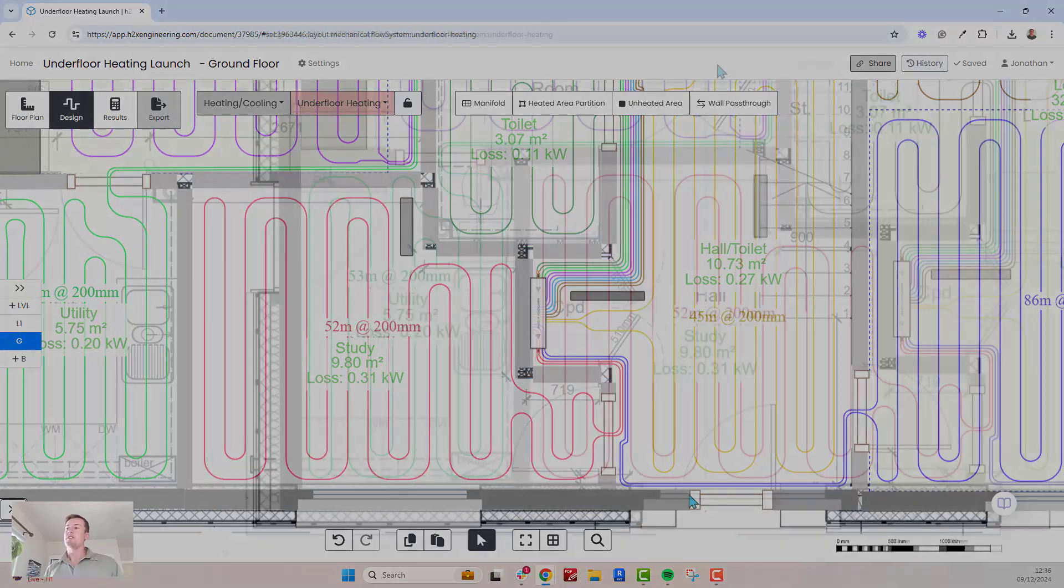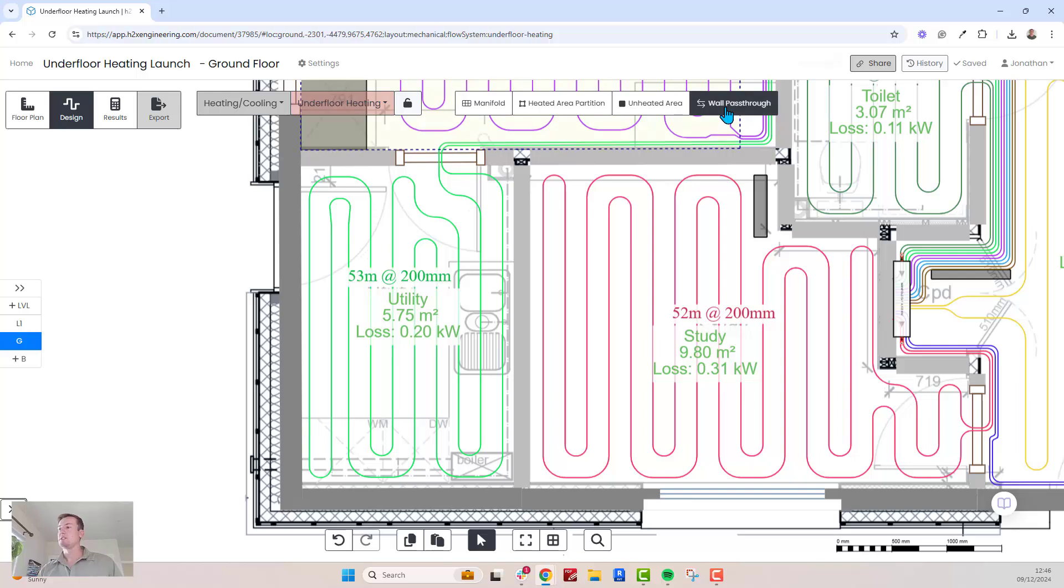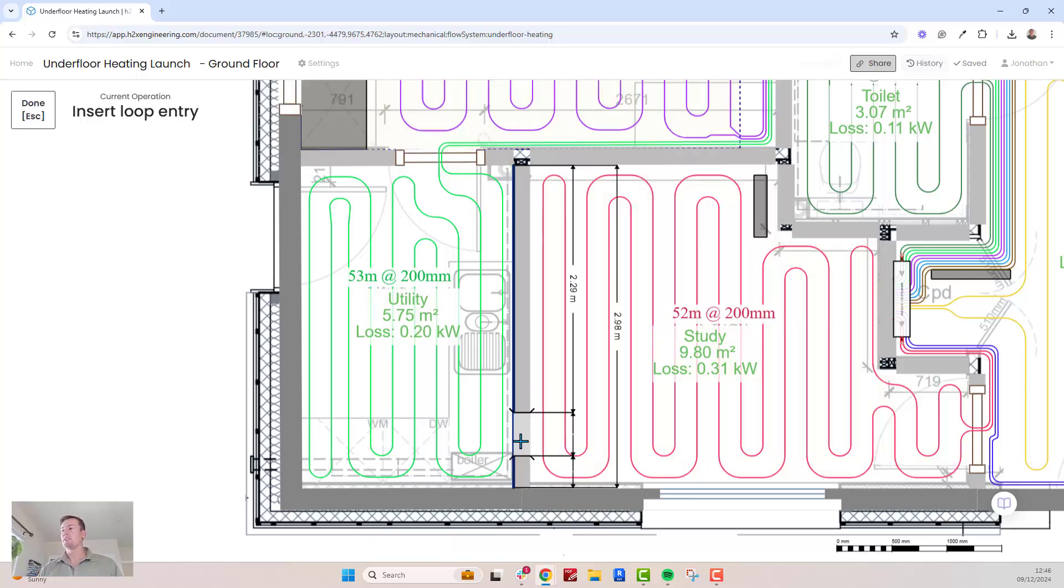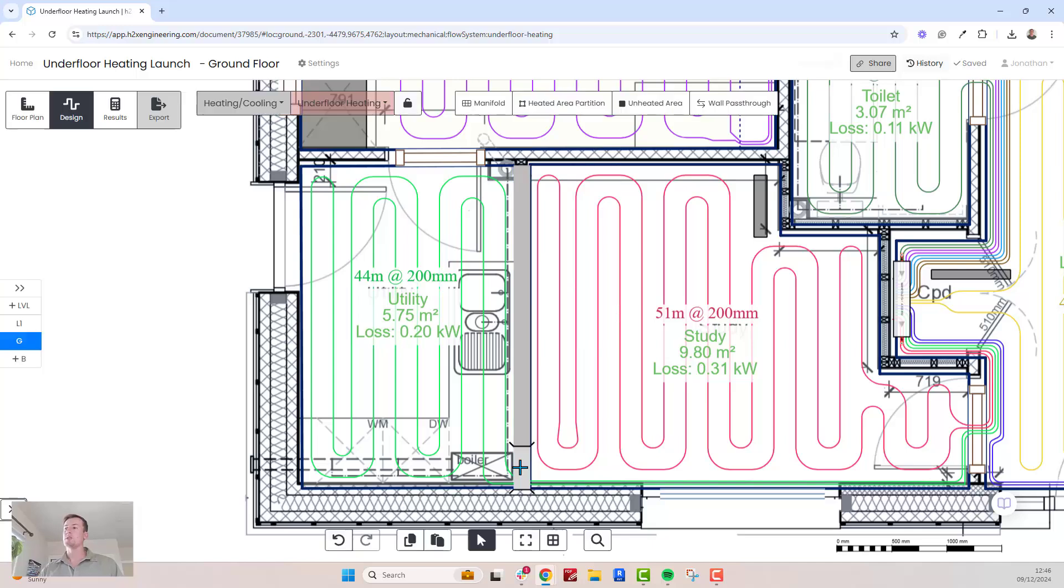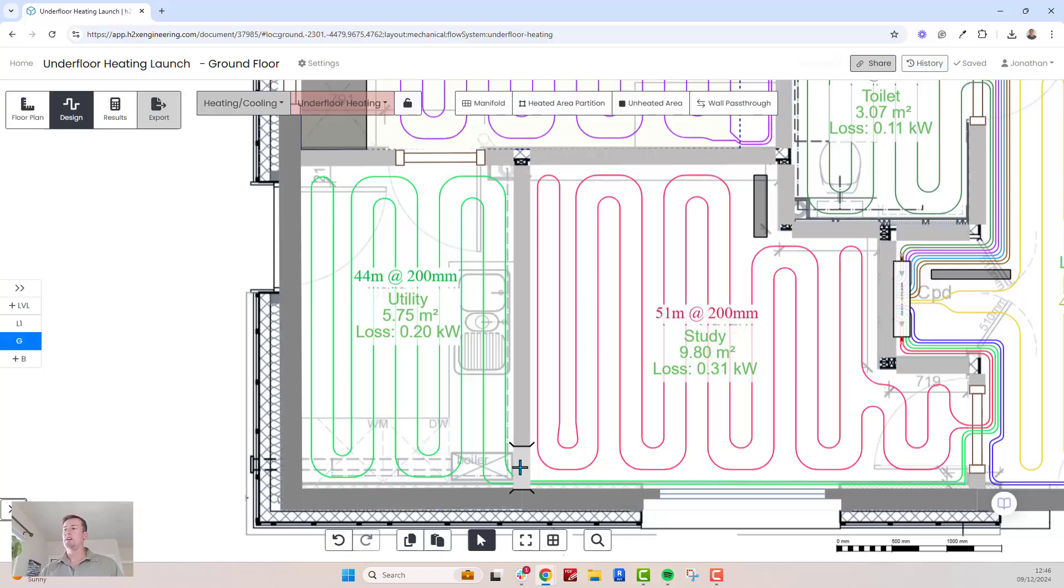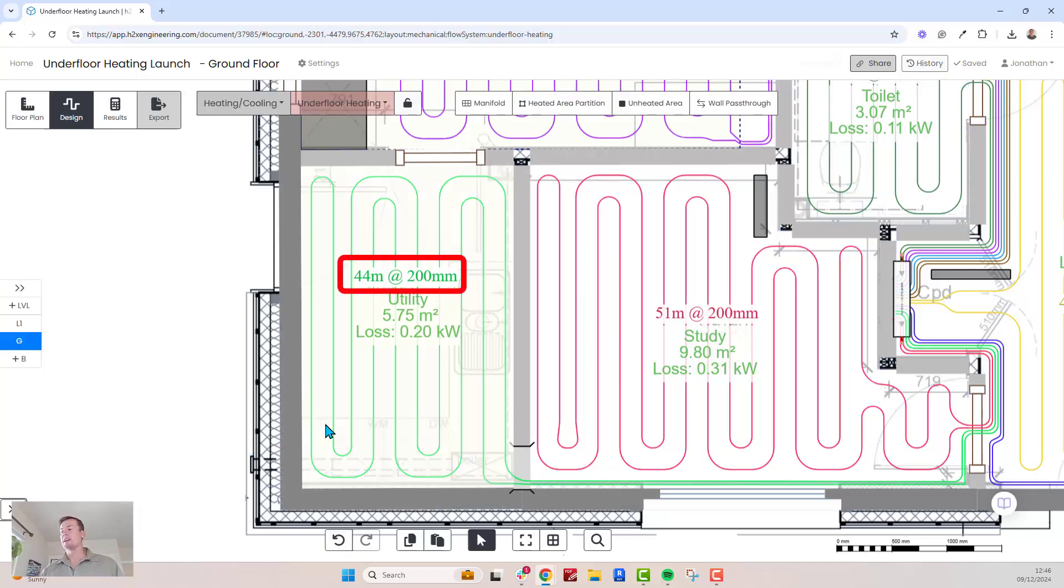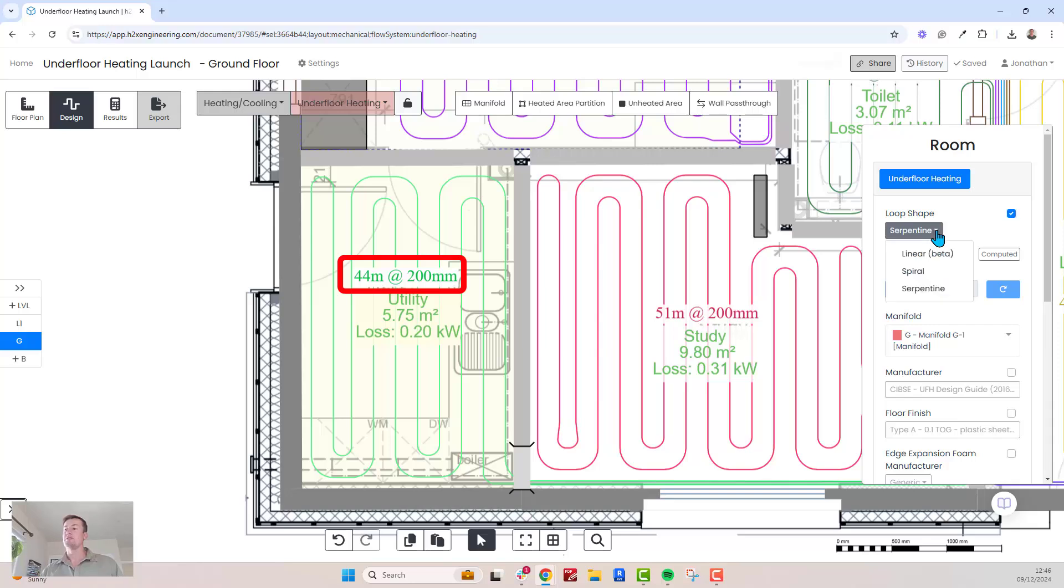The software will always optimize loop layouts to minimize pipe usage. If you ever need to refine your design, you can add wall pass-throughs and this will adjust the loop path. For example, in this room we can add a wall pass-through so the transit pipes can come the opposite way. This reduces the length from 53 meters to 44 meters.